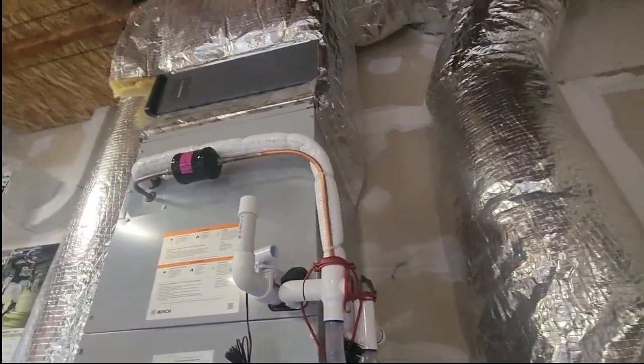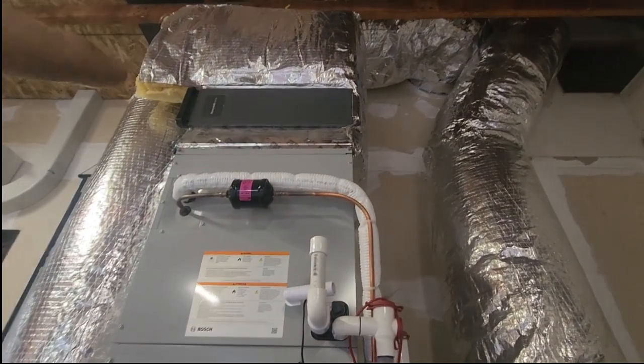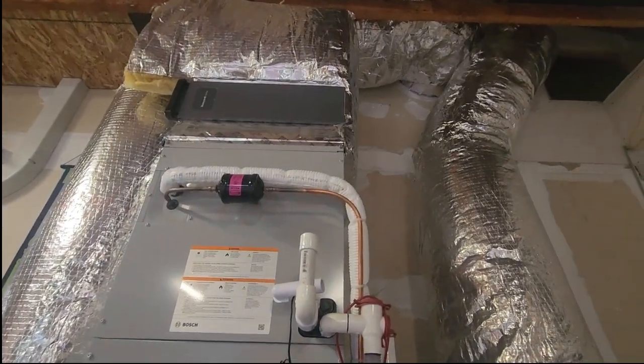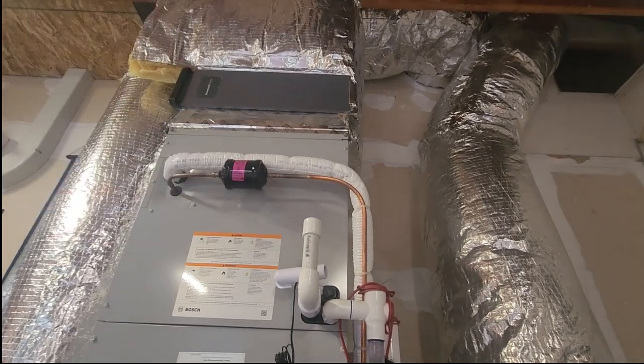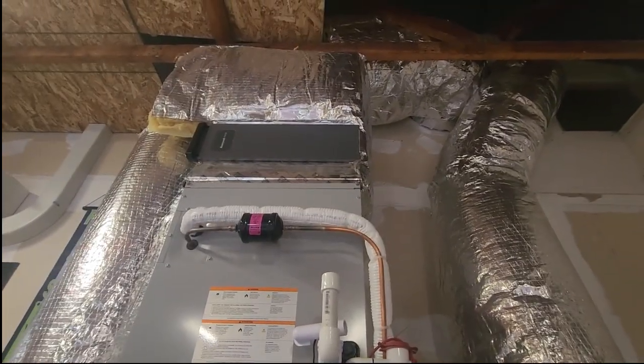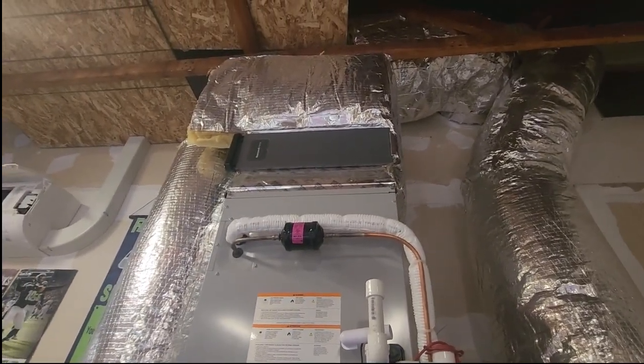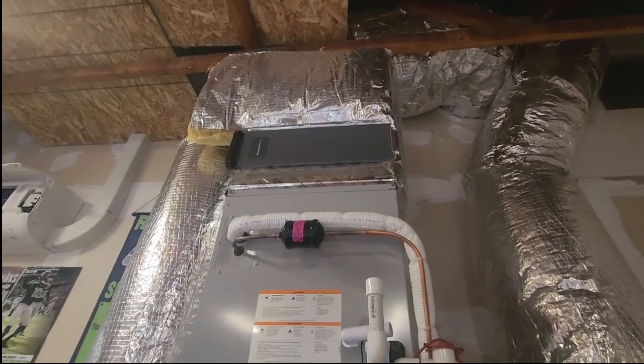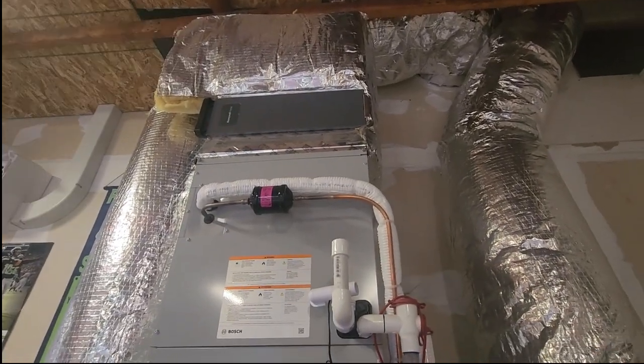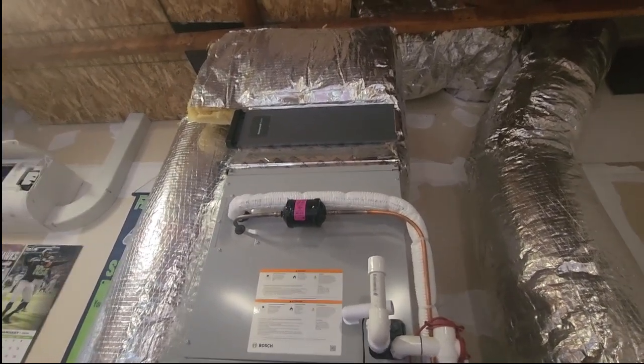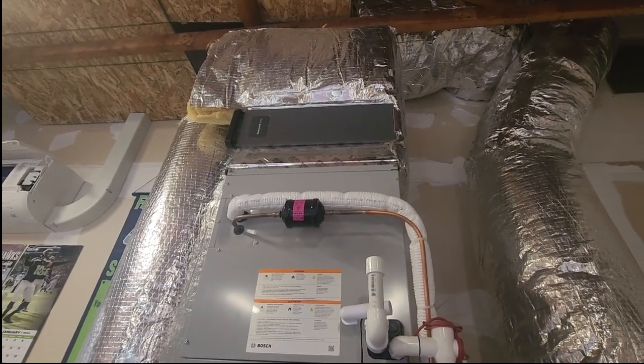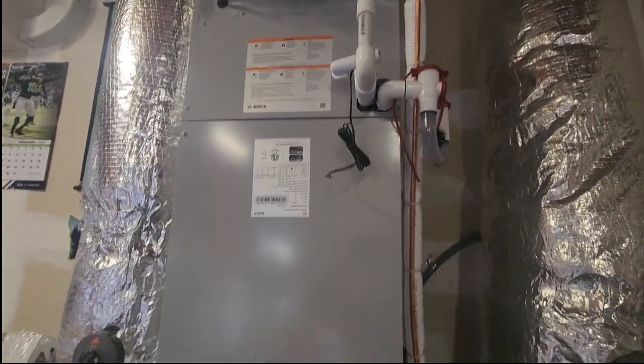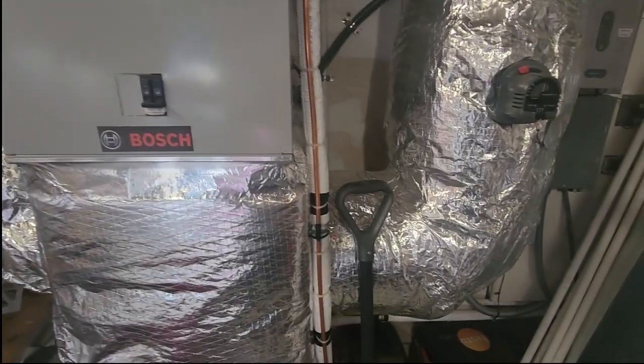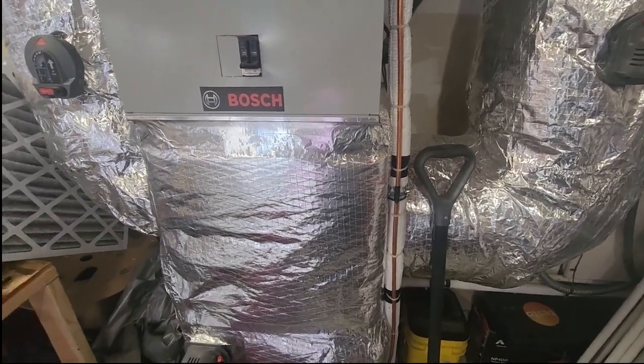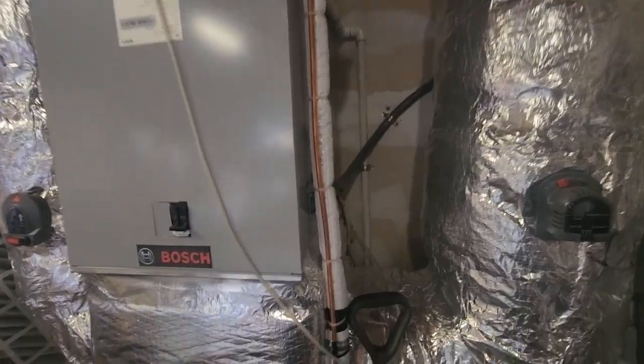I've got a spacer. I always put a spacer between the air handler and the filter, so I'll be able to get a probe there and a probe there and see what the filter's giving us. I just replaced the filter, so that'll be a good lesson on what static pressure these 4-inch filters have when they're clean. I'll get some holes drilled in, get the equipment set up, and show you how that works, and force this thing into cooling, both zones. I'll be back.